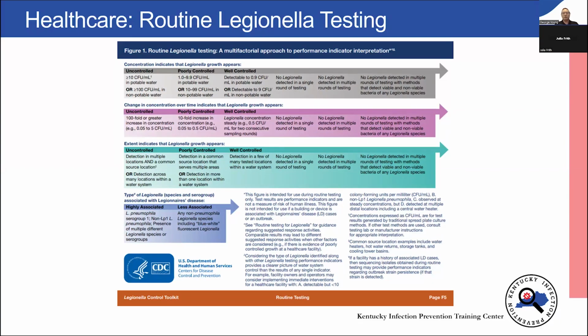But if you're in that poorly controlled situation, you'll need to figure out whether you're going to do flushing, a shock disinfection, or look at secondary disinfection for your potable water system. That is what you will write into your water management plan. You'll write, we are going to use Legionella testing on a quarterly basis at 20 sites within our facility. That is our validation step. If any of those sites are positive, above the CDC or your own recommendation of 1 CFU per mL, or whatever you determine you want that to be, then we are going to institute an intervention at that location and/or associated locations.